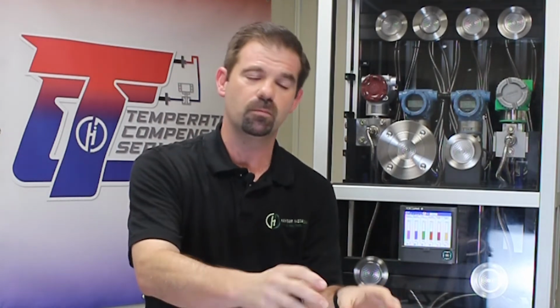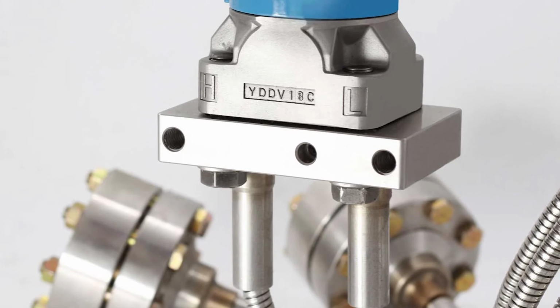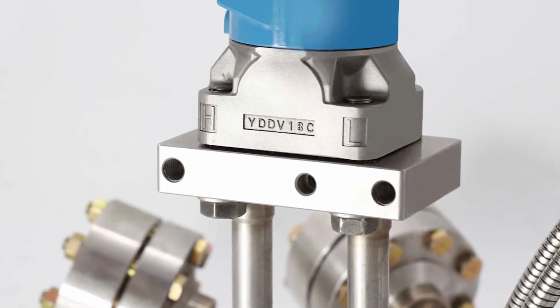When you get direct sunlight, or you get temperature shift from morning to the afternoon to the evening, when that temperature changes on that capillary, both sides of that capillary heat up or both sides cool off at the same time, and the expansion or the contraction with the oil in both of those tubes offset each other because one side is connected to the high side and the other side is connected to the low side, and vice versa for the other side.